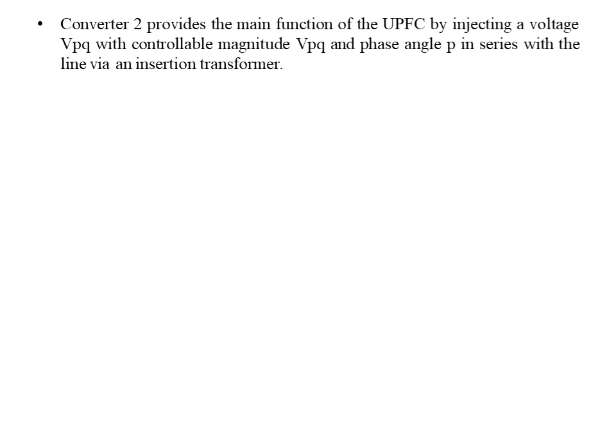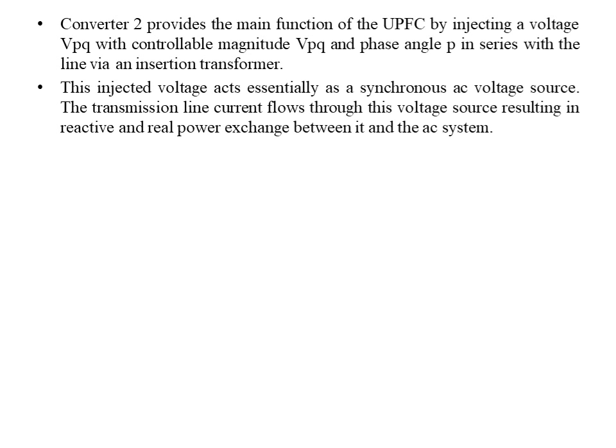Converter 2 provides the main function of the UPFC by injecting voltage Vpq with controllable magnitude Vpq and phase angle Rho in series with the line via an insertion transformer. Out of the two converters, Converter 2 injects the voltage Vpq into the system with phase angle Rho in series with the line using an injection transformer. This injected voltage acts essentially as a synchronous AC voltage source, and the transmission line current flows through this voltage source resulting in reactive and real power exchange between it and the AC system.